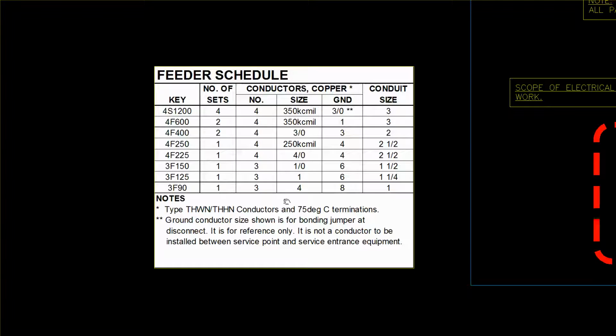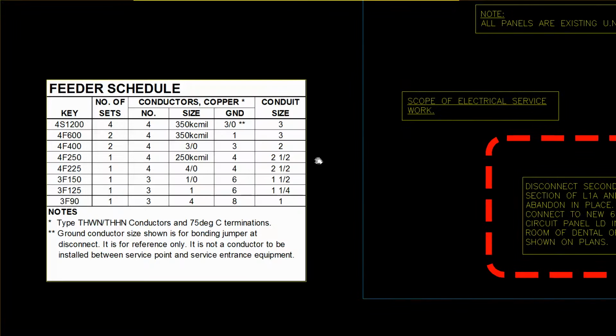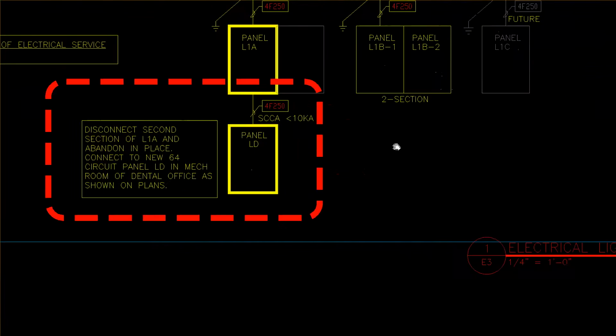I've got to be a little careful because I may leave one off. Maybe I have a 3F 175 or a 4F 175 that I needed on the schedule, but then I forget to add it to my feeder schedule. Well, then there's a little bit of a problem. Somebody has to issue an RFI to get that accomplished. A lot of times it gets caught in plan review, and somebody will come in and say, hey, look, you're missing a feeder for that. We want to know what that is, and that's a good use.